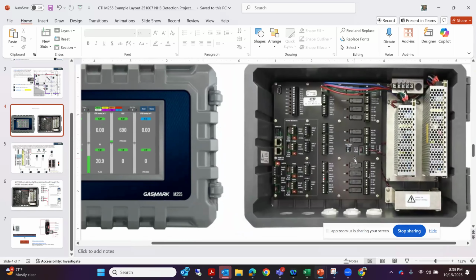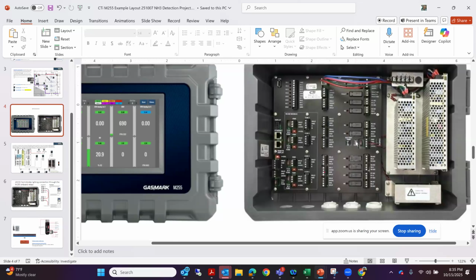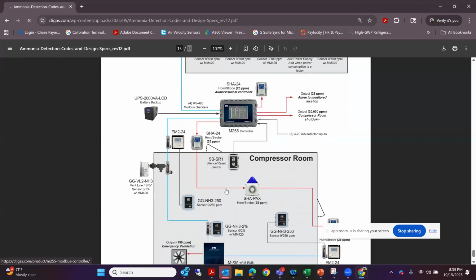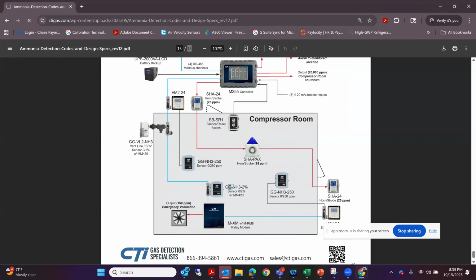But they do say that the system does have to be 100% shut down and de-energized by 25% of the LEL, and the sensors that we're talking about here, in the compressor room, they're doing it way, way, way ahead of time, right? I always say that the old number used to be 16% for the LFL, the lower flammability limit for ammonia. It's actually closer to 15, but I always said 16 because it made it easier to say, okay, what's 25% of 16? Well, 16% is 160,000 ppm. Well, 25% of that is 40,000 ppm. So the magic number is 40,000 ppm if you're calling the flammability point 16%.